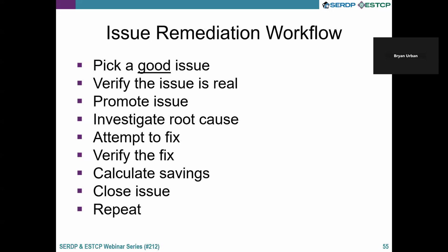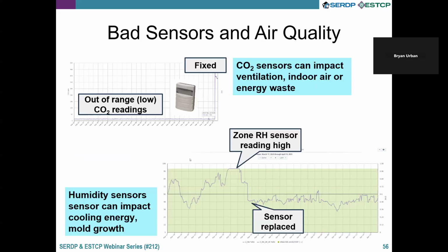So that's kind of the workflow. And now we'll talk about some of the actual issues that we found. These are just a flavor of some of the examples. The first thing we found at Air Station Beaufort was about a dozen CO2 sensors that were reading very low. Something was wrong and they were reading close to 0. So they got that fixed, and you can see at the top of that graph that they're reading a normal value after that. But that can affect ventilation rates, indoor air quality, waste energy, and cause other kinds of problems.